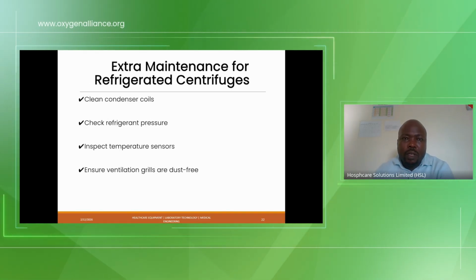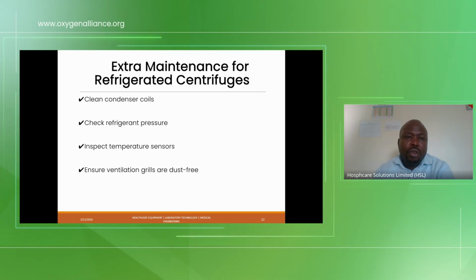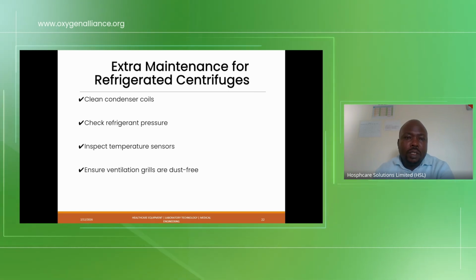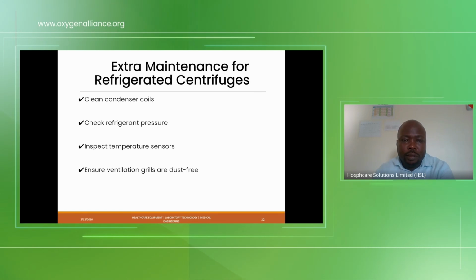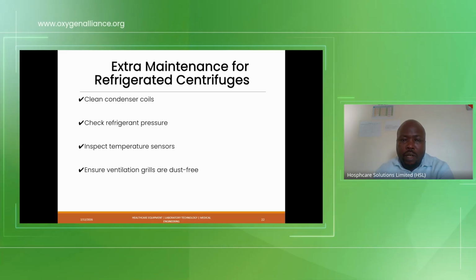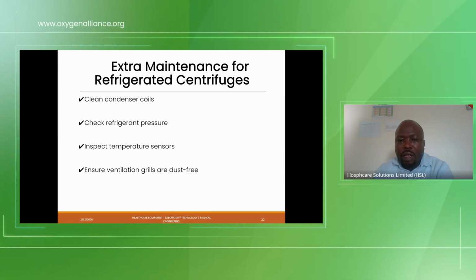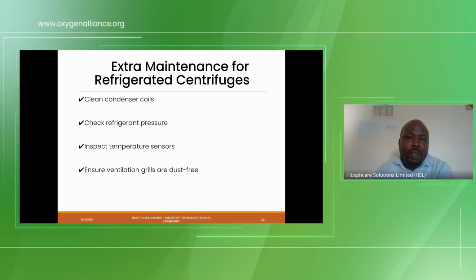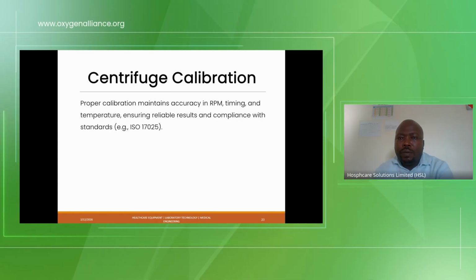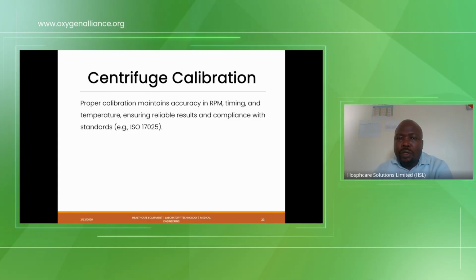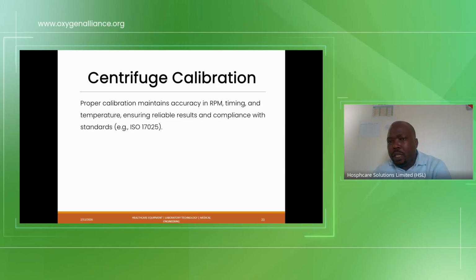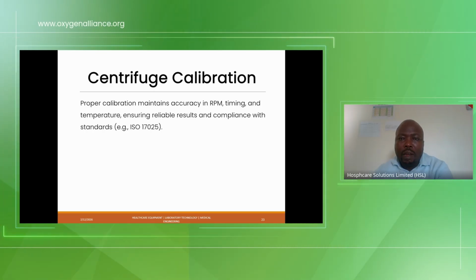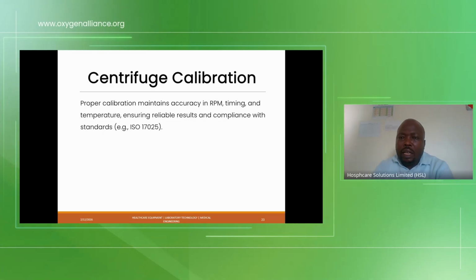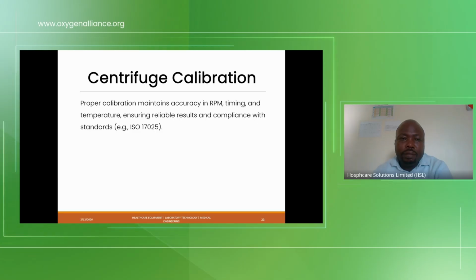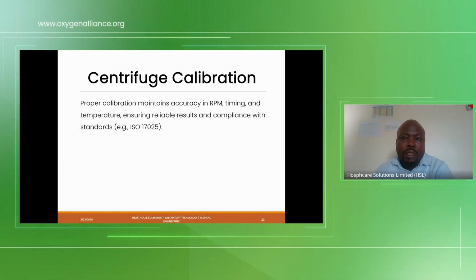In the case of a refrigerated centrifuge, you need to clean the condenser and coils, check refrigerant pressure, inspect temperature sensors, and ensure ventilation grills are dust-free by blowing off the dust. Centrifuge calibration: proper calibration maintains accuracy in revolutions per minute, timing, and temperature, ensuring reliable results and compliance with standards. I will explain how you do this calibration.